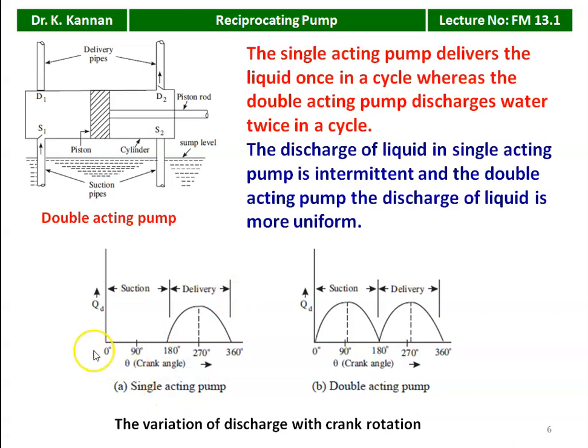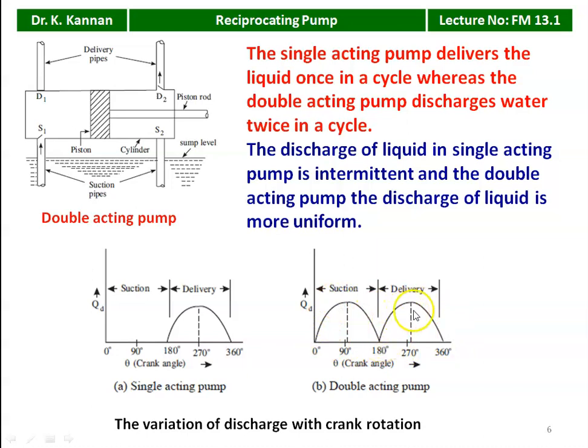From the diagram, in a single acting pump during the suction stroke (0 to 180 degrees), water is drawn inside; during the delivery stroke (180 to 360 degrees), water is compressed and delivered — so it delivers liquid once per cycle. In a double acting pump, water is discharged twice per cycle — in every stroke, one side has suction and the other has delivery, giving continuous delivery. The discharge of liquid in a single acting pump is intermittent, whereas in a double acting pump the discharge is more uniform and continuous.